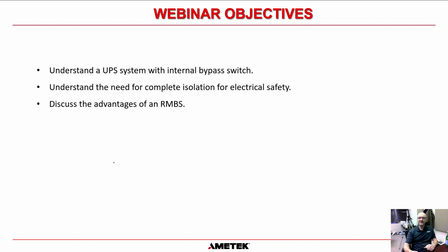So the objectives today are going to be: understand a UPS system that has an internal bypass switch. In other words, it's integral to the UPS itself. It's not outside of the UPS cabinet. Understand the need for complete isolation for electrical safety, and discuss the advantages of an RMBS, a remote manual bypass switch, which is completely external and separate to the UPS system.